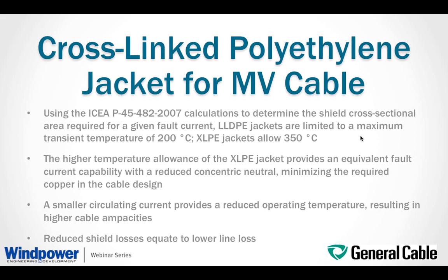So typically the cables are designed to meet the requirements of ICEA P45-482, and how do you calculate your required cross section of your shield to meet a given fault current? For a thermoplastic LLDPE jacket, they are limited to a maximum transient temperature of 200 degrees C, whereas with a thermoset XLPE jacket, the standard allows going up to 350 degrees C.